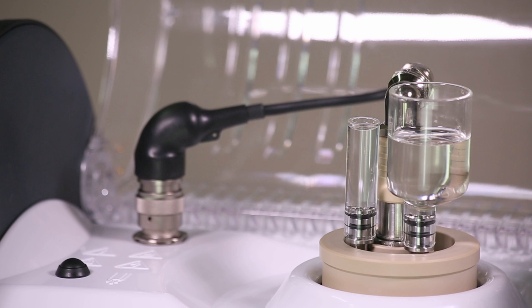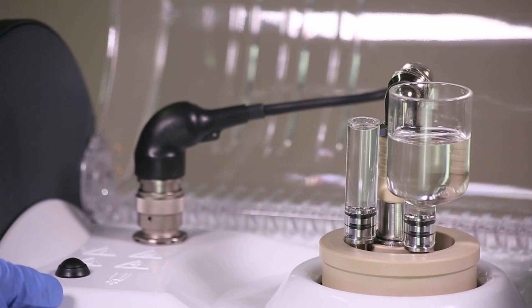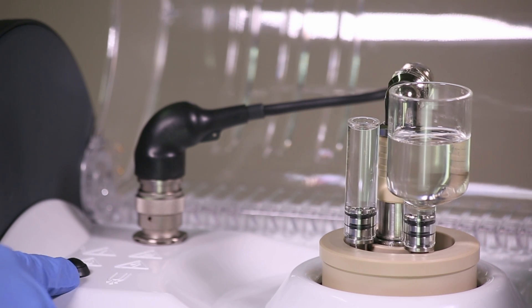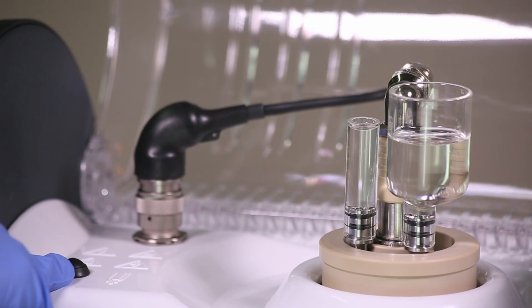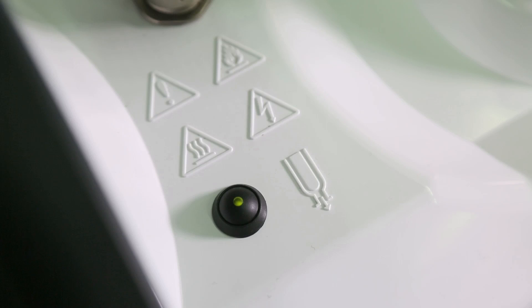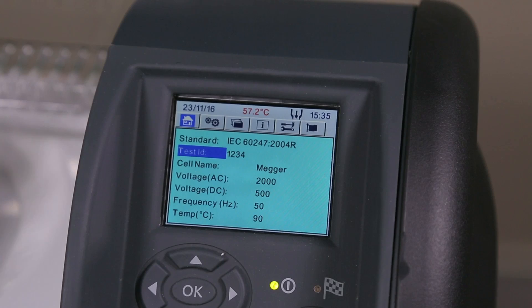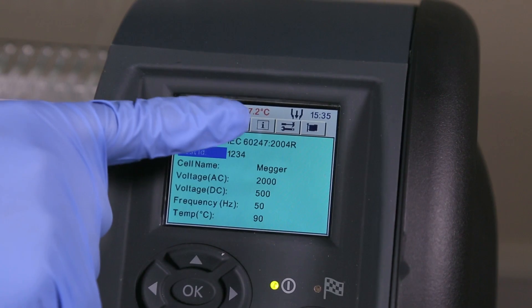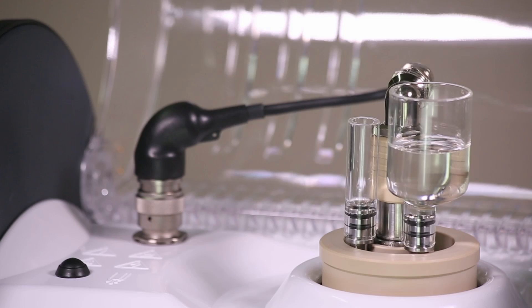When finished, the oil can be drained manually by pressing the oil drain button inside the lid. The green LED will light up and a symbol on screen will show while this takes place.